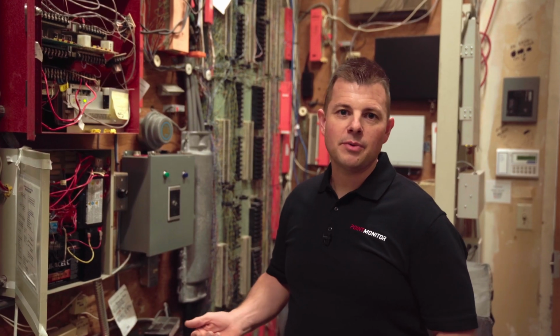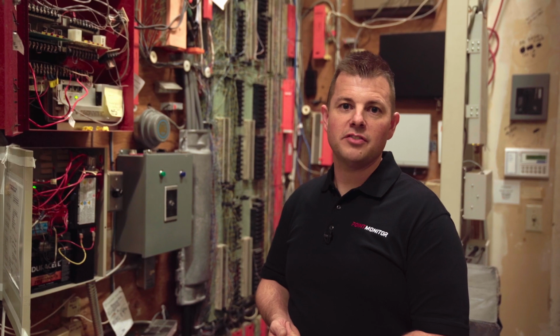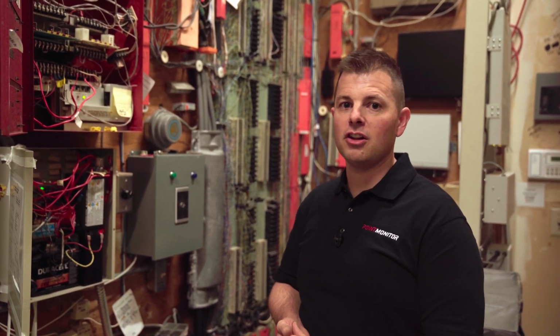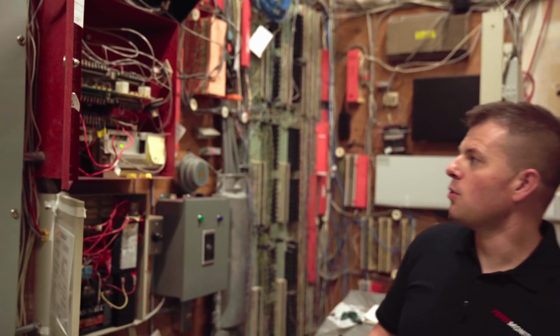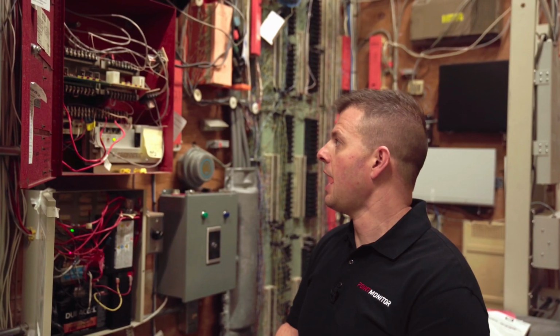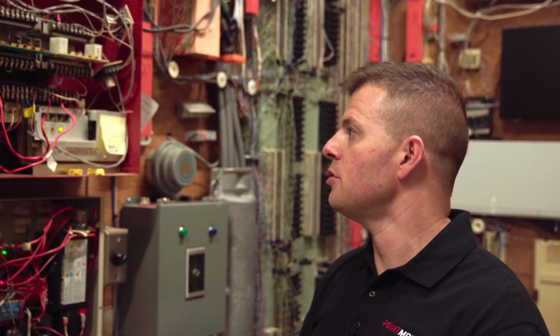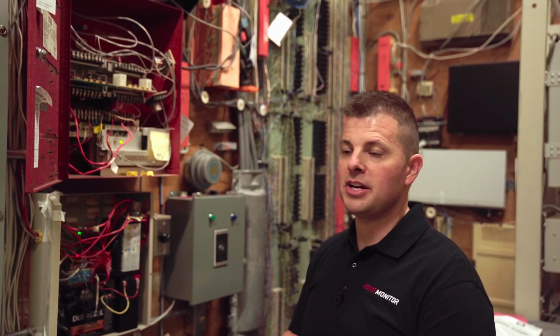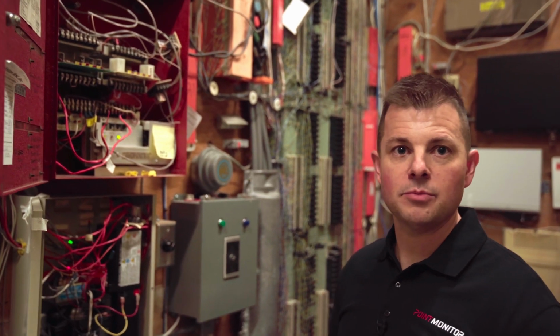The fire alarm system that we're often replacing will consist of a lot of initiating devices and fire alarm outputs. We'll transition these circuits over from the old system to the new in an order that makes sense along with the construction schedule. As we walk into an old system, they don't look anything like what's going in, so we have to determine how it operated and how it communicated in order to take over those functions and make sure that both systems operate within code.